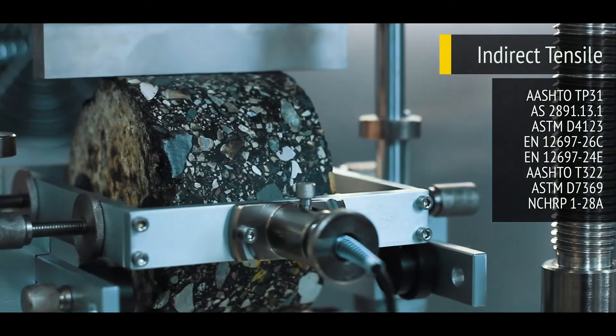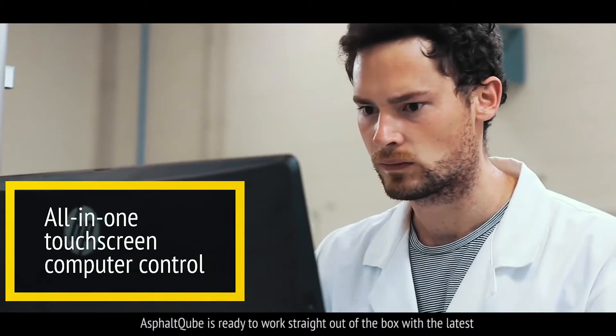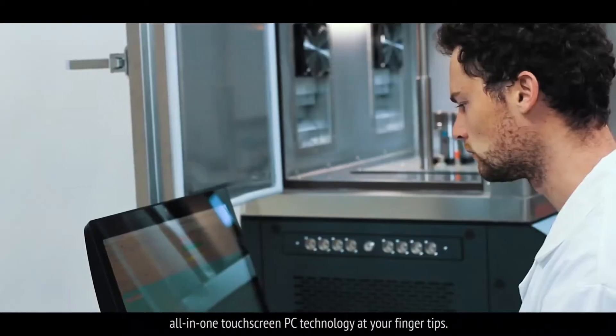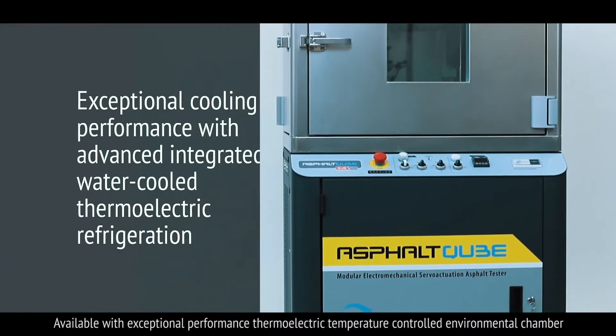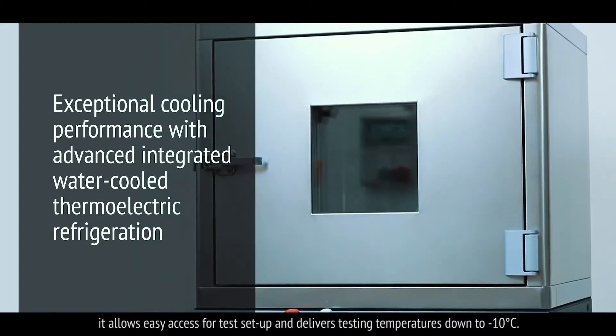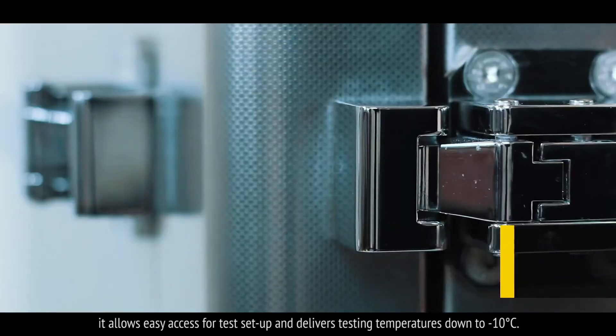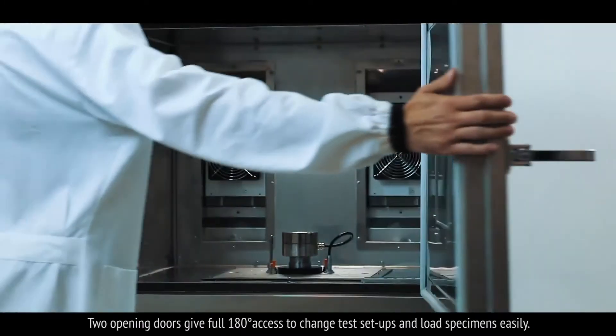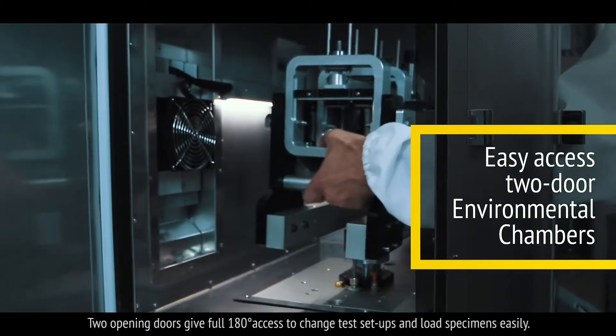And indirect tensile. AsphaltQube is ready to work straight out of the box with the latest all-in-one touchscreen PC technology right at your fingertips. Available with exceptional performance thermoelectric temperature controlled environmental chamber, it allows easy access for test setup and delivers testing temperatures down to minus 10 degrees Celsius. Two opening doors give full 180 degree access to change test setups and load specimens easily.